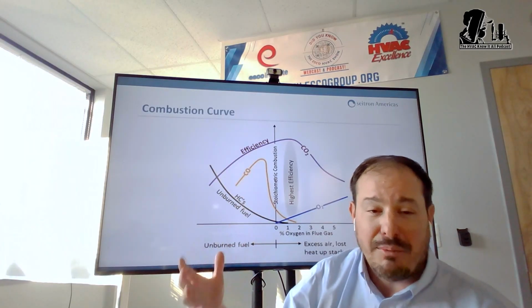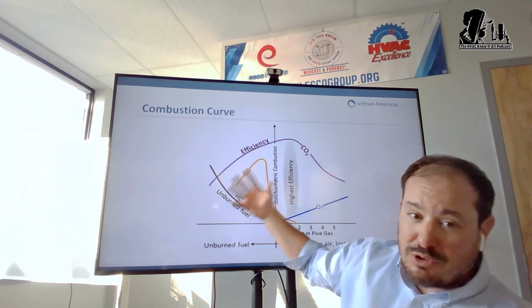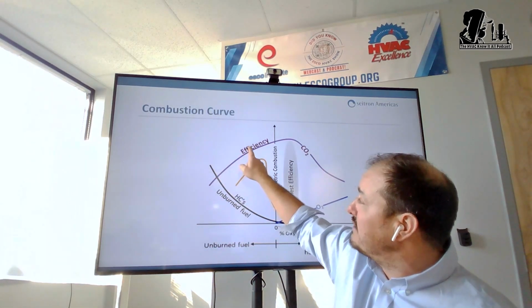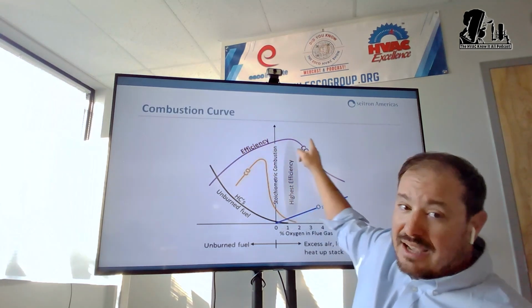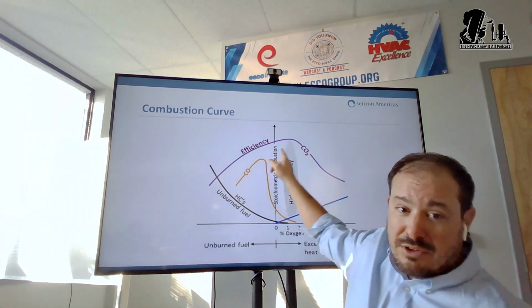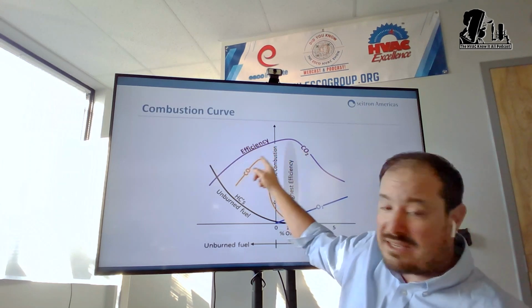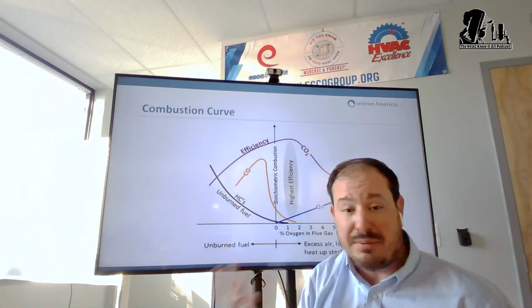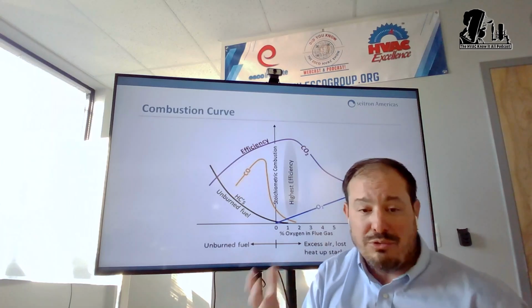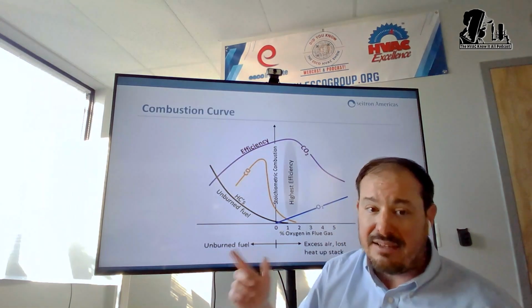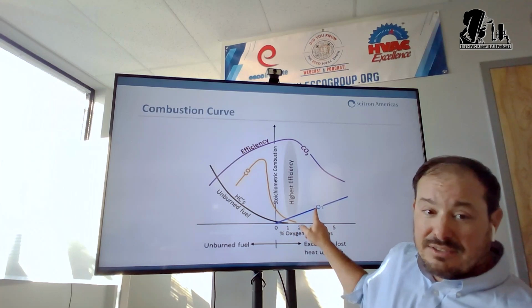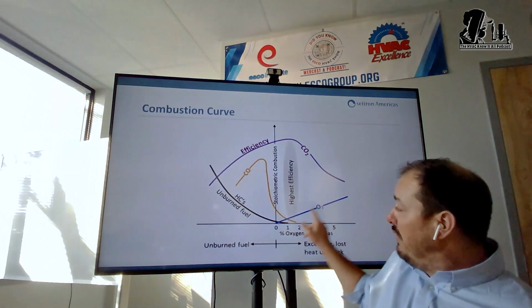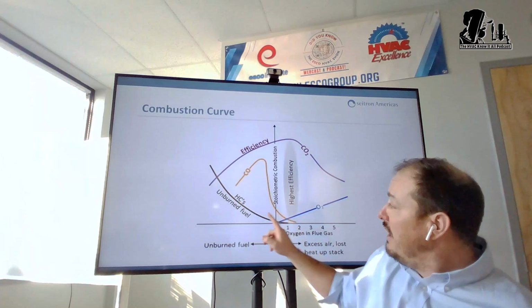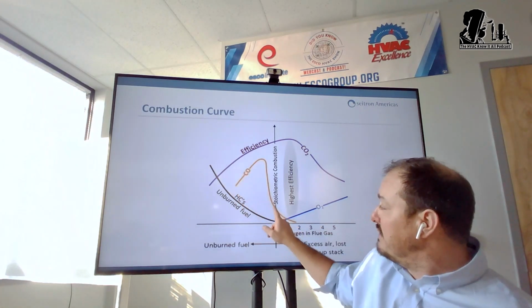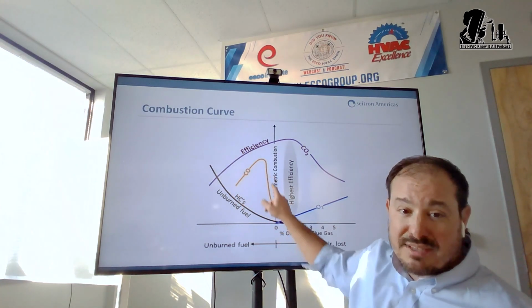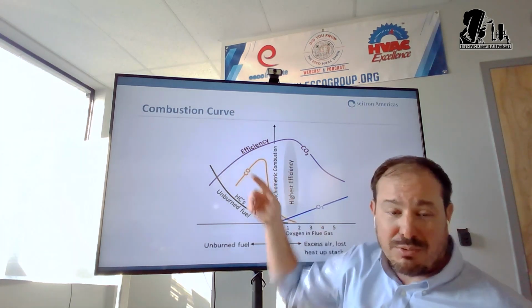So the reason why it's called a stoichiometric curve is because, and the problem we have, if you notice what a curve does, you can actually have the same CO2 number on either side of the curve. So if we only look for CO2, we're not potentially seeing other problems, and the flame could potentially look the same. So you don't know what side of the fence you're on, which is, again, why analyzers have two sensors. Your oxygen sensor to tell me, am I running on the air-rich side and how much excess air do I have? And a CO sensor to tell me, based on safety, if I'm on the wrong side of the curve. I don't really care so much what CO2 is anymore.